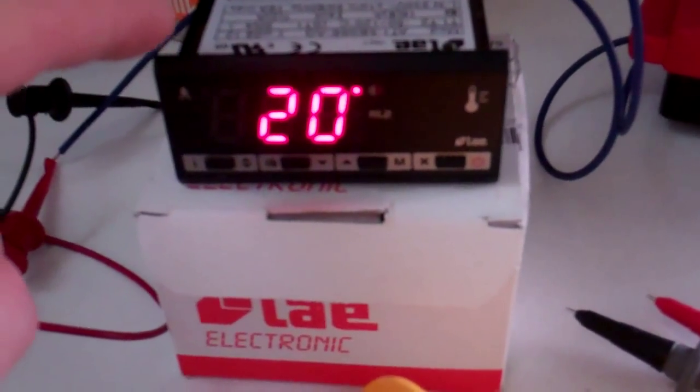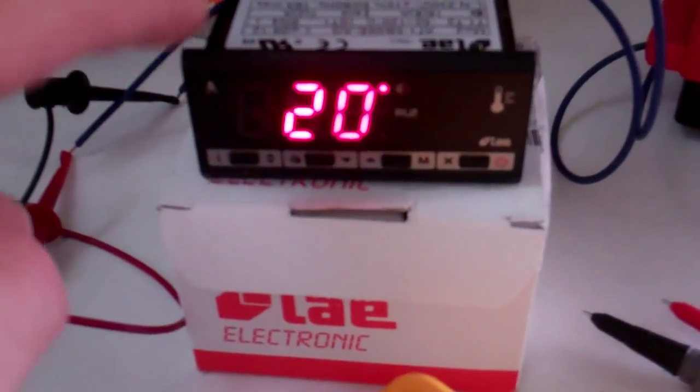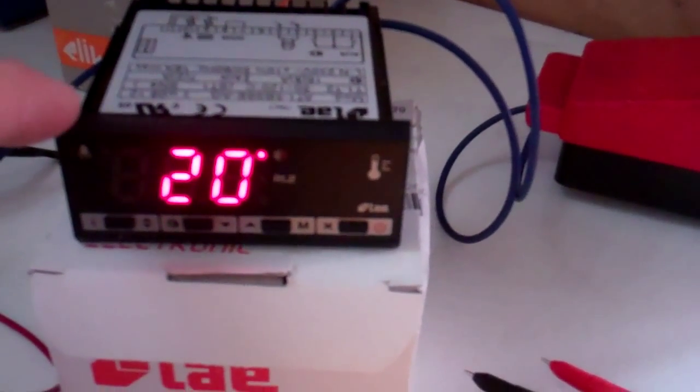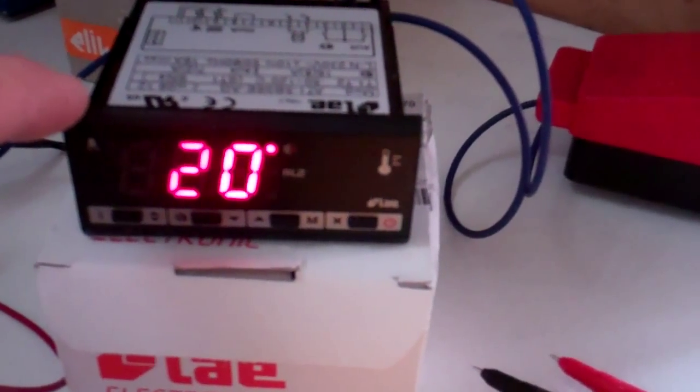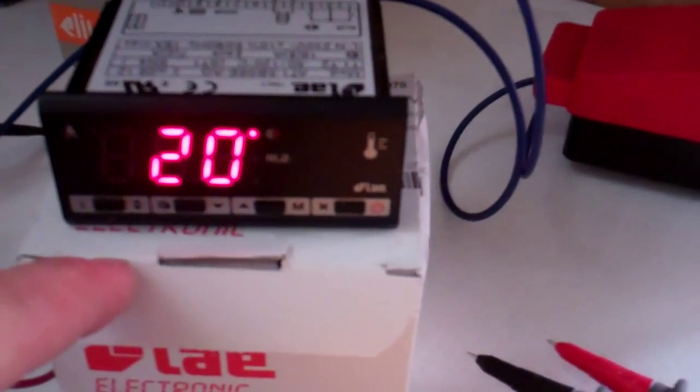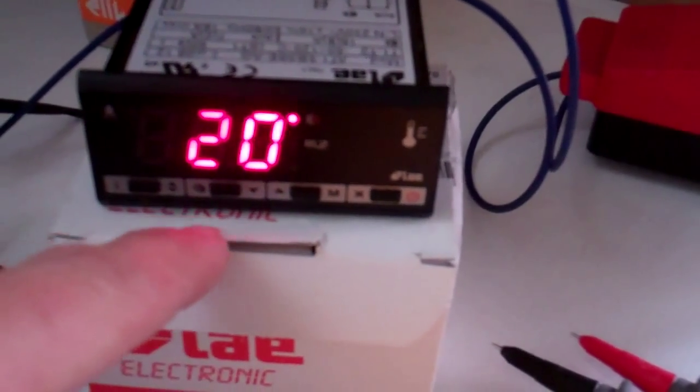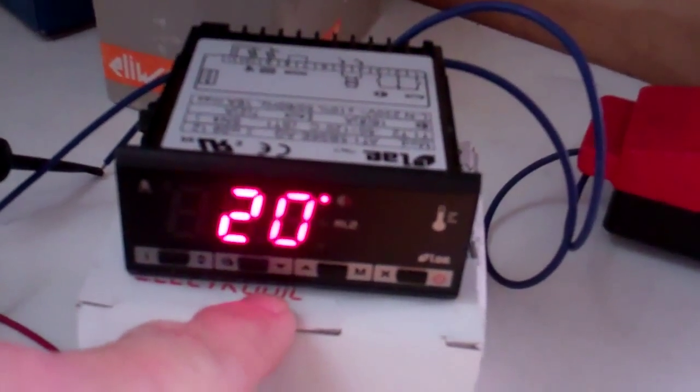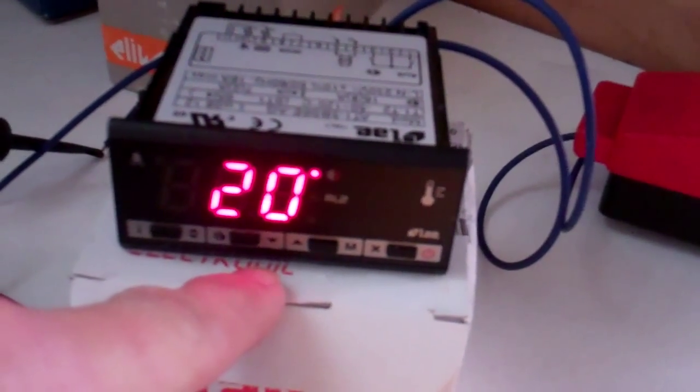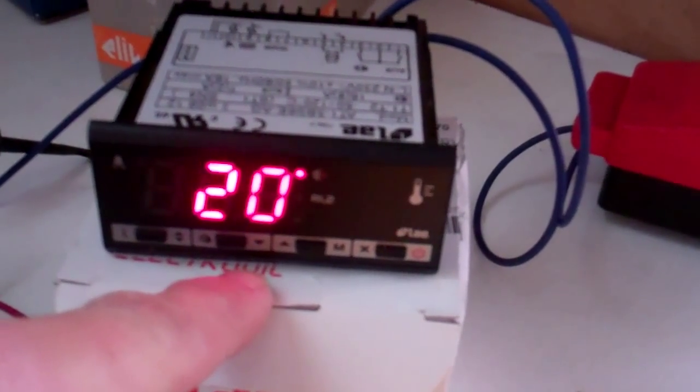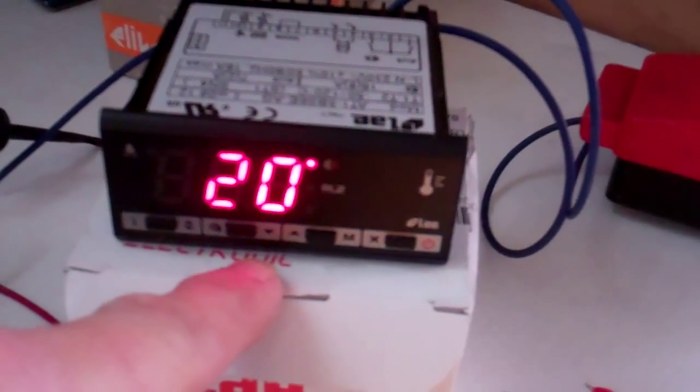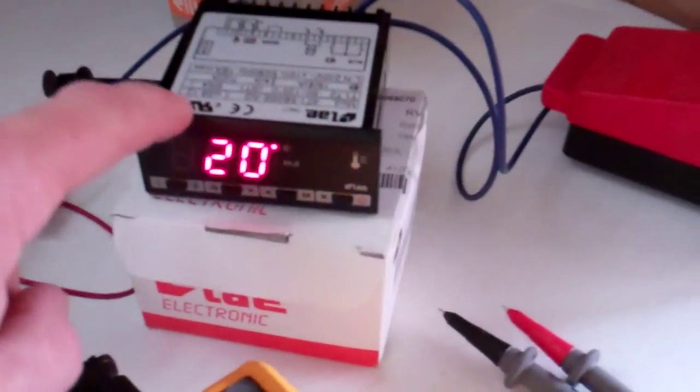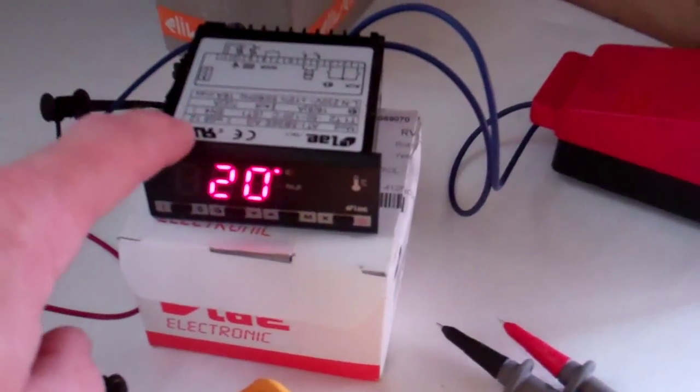So what I thought it would be handy to be able to do is know what resistance you should have at a set temperature. So this is reading 20 degrees at the moment. I've got one probe wired in which is the evaporator probe, so it doesn't bring up a fault code. It will come up with an E2 fault if there's no probe connected.